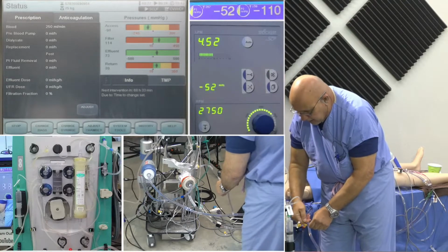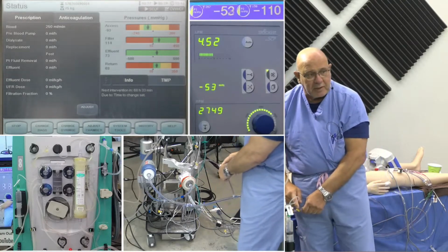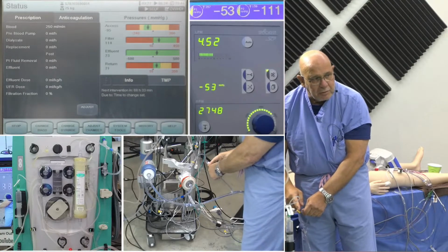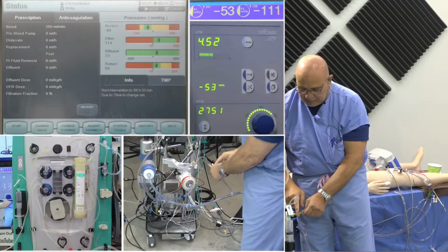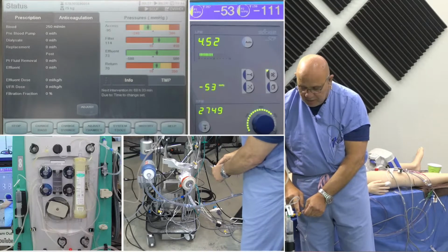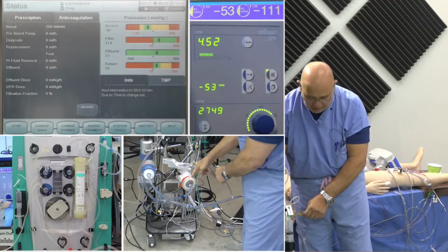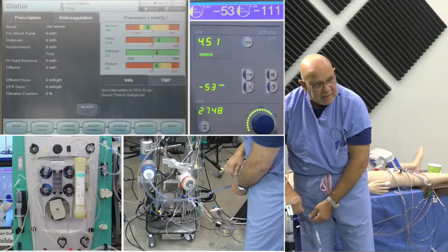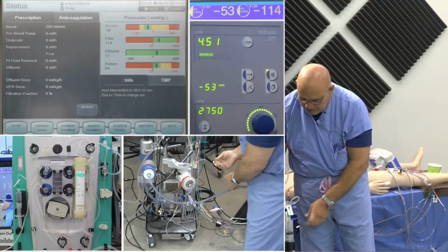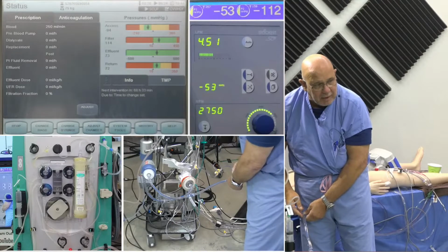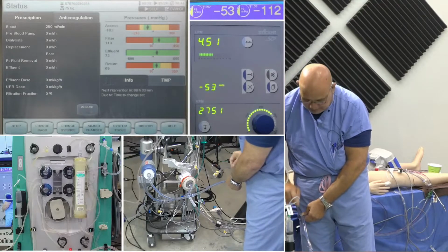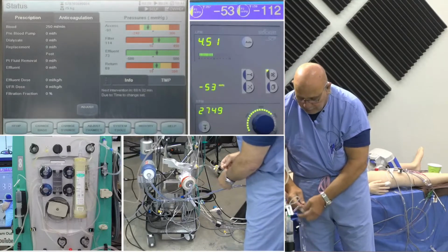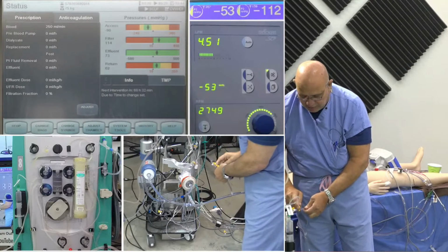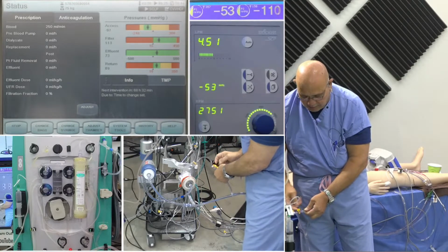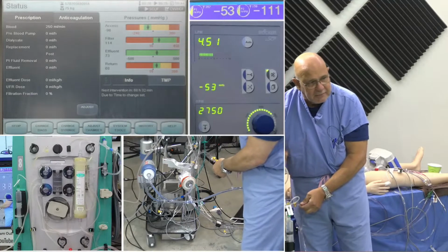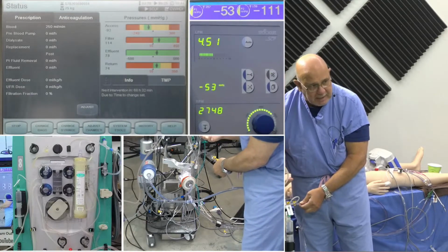And again, what I said is you have to be very careful. You have to be very thoughtful before you go pulling things off of these stopcocks, two things. One, you'll notice there's no stopcock on any of the connectors. They're always pigtails. You never want to put a stopcock on the connector. It'll break off, and there's nothing you can do about it. This is not going to break off. But the risk is if I turn this stopcock this way, take this off, it's going to suck full of air. It's a different scenario, but it can happen.